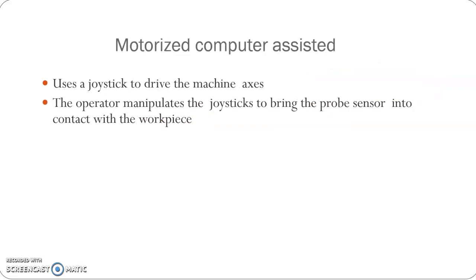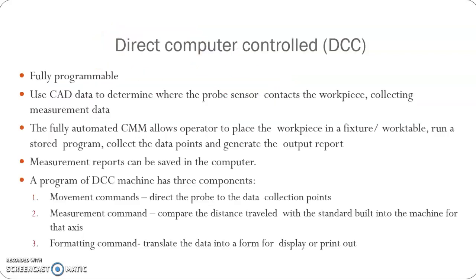In motorized computer assisted, the computer assistance is the same as in the previous case, but the movement of the probe in XYZ directions are actually motorized, not manual. A joystick is provided to drive the machine axes. Using XYZ axis joysticks, we can move the probe in all the axes.